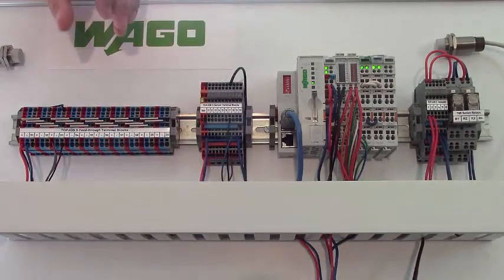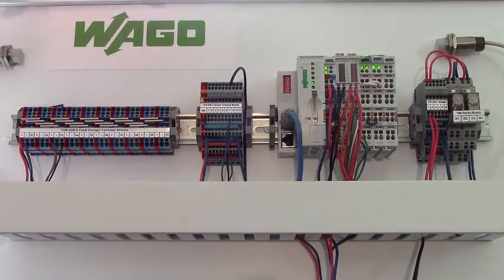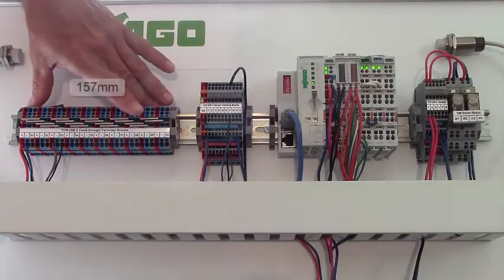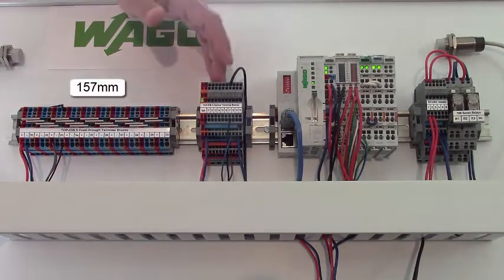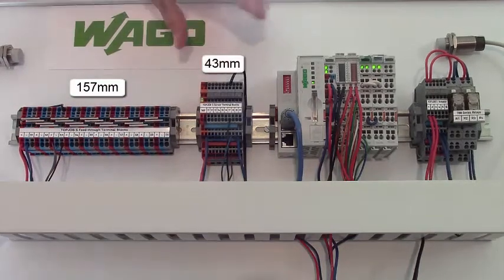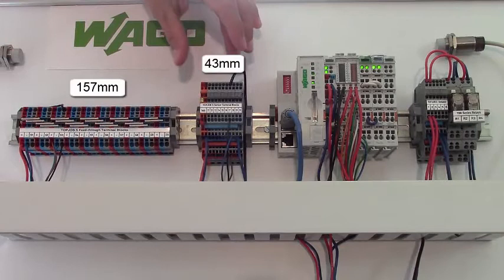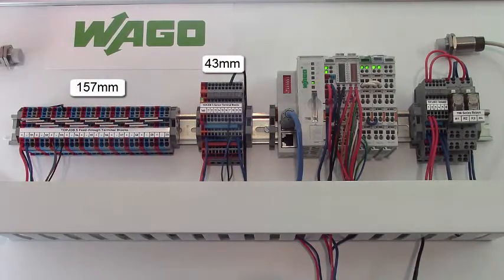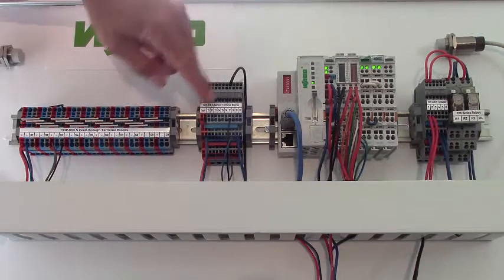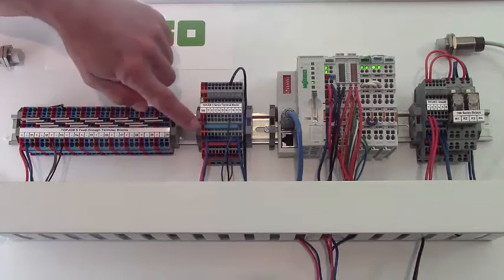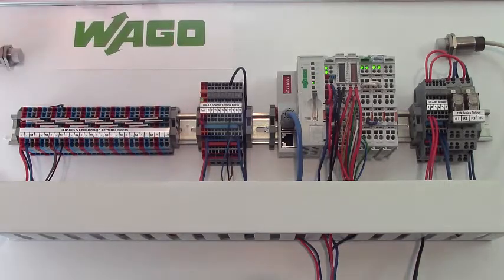So immediately you can see that the standard TOPJOB S series terminals take up approximately 157 millimeters, while the TOPJOB S series sensor blocks only take up about 43 millimeters. Also you'll notice how much easier it is to utilize the jumpers for the sensor blocks. There are only two jumper types here for the color coding jumpers for the power, so for your plus and minus.